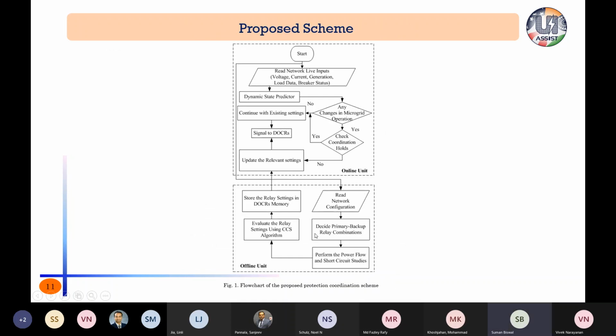So basically what we are doing here, the optimization part will calculate all the relay settings for all the topologies, the topologies which are very essential. For that set of topologies, the settings need to be calculated. So the algorithm starts here. As you can see, we have an online unit and an offline unit. All the optimization part will be included in the offline part. It will read the system configuration, whether it's grid connected or islanded mode or any other configuration. Based on that, it will decide the primary and backup relays.